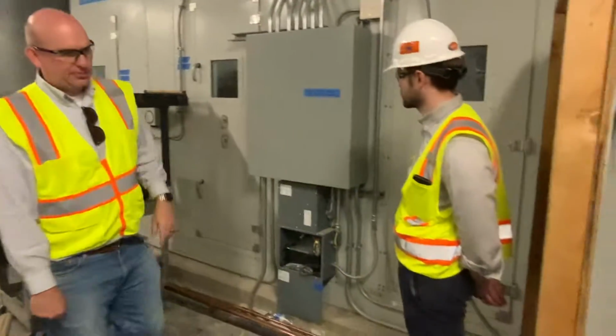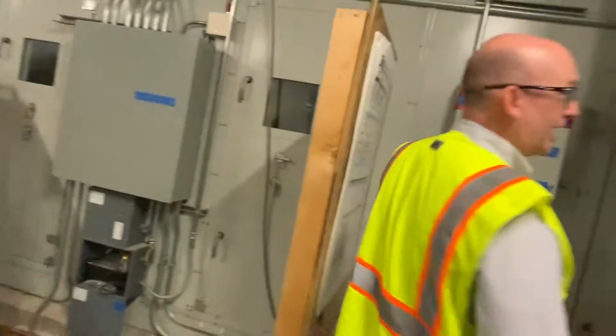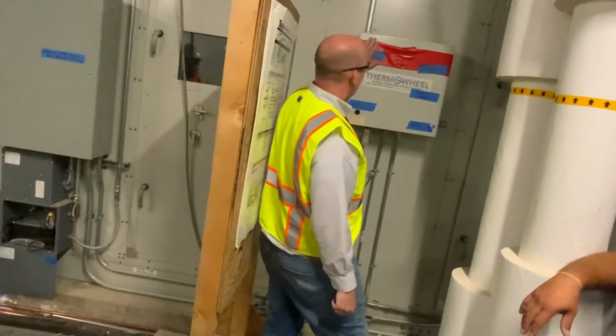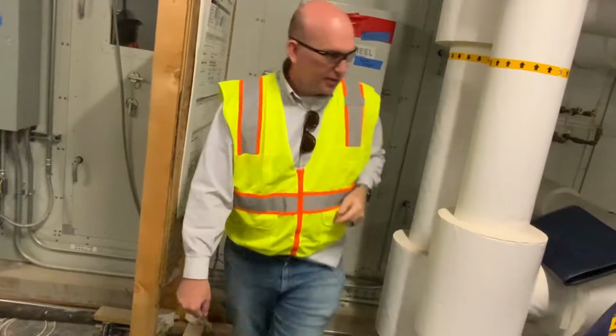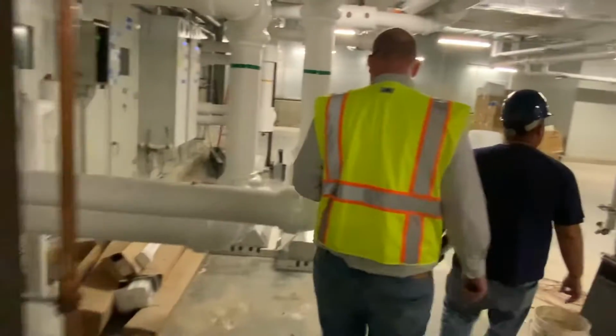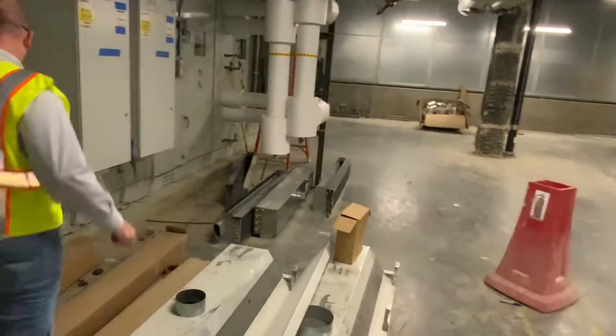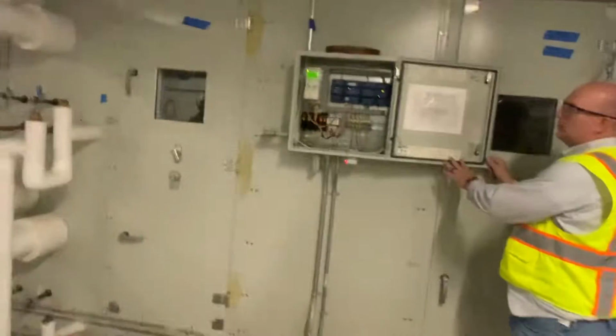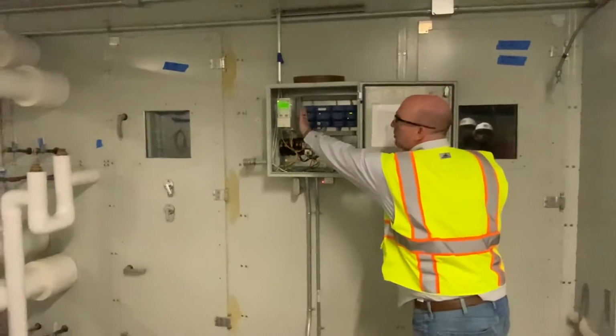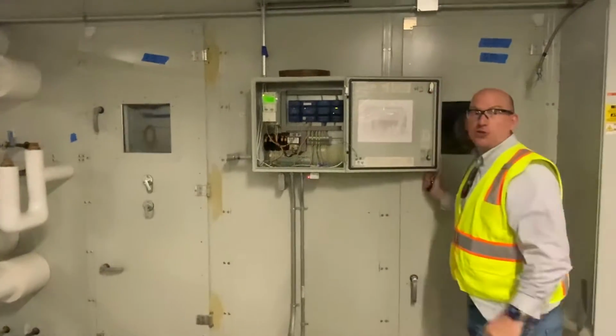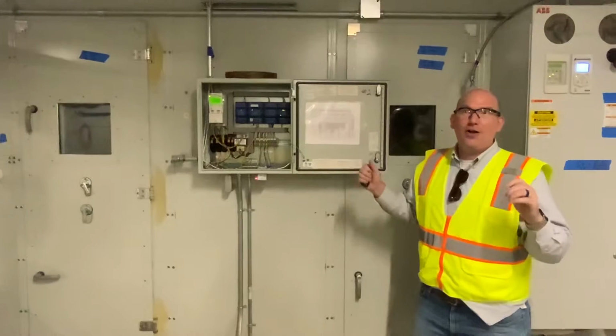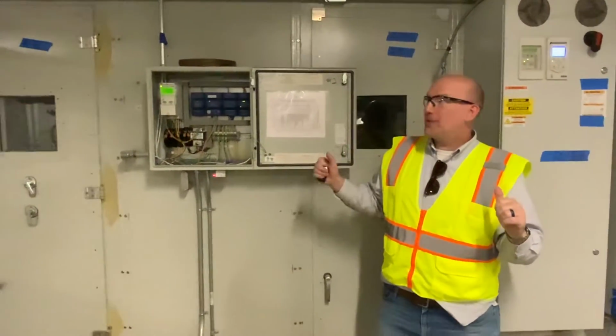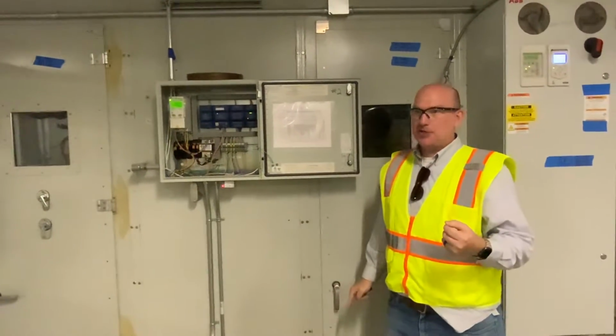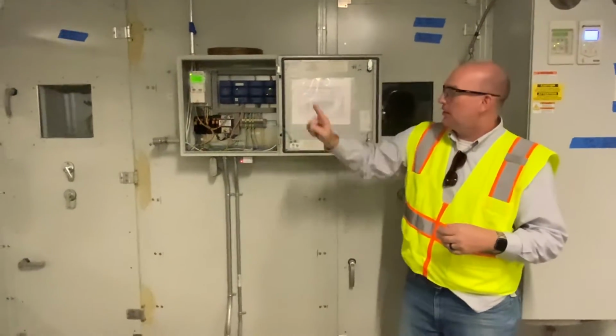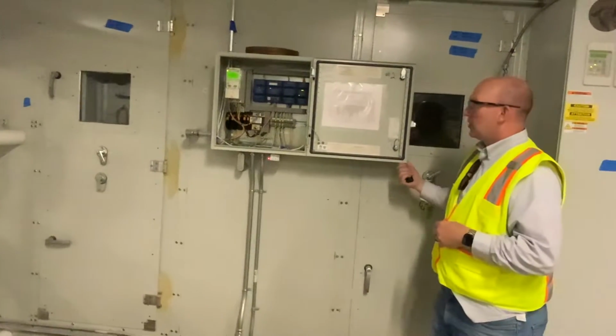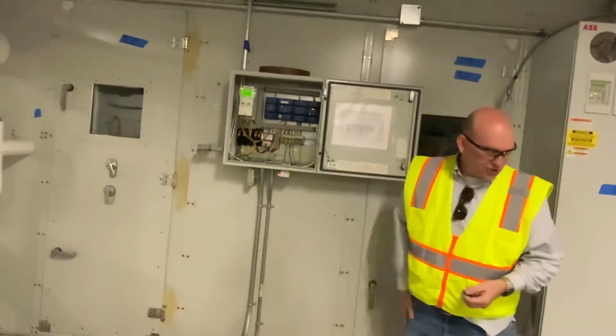The two wheels that we talked about earlier, that's these, obviously giant Thermotech. I don't have my special Thermotech key. That's this enclosure, and then the second enclosure is over here, which is open, so we can actually look inside of that one. So, a small ABB VFD, a Distech controller, and that's what controls the wheels. There are 4-point temperature sensors on the Sensible wheel, and there are 4-point temperature sensors on the Total wheel, and 3-point enthalpy. So you have 3 points of monitoring of humidity on that wheel, no humidity monitoring on the Sensible wheel. And that's it.